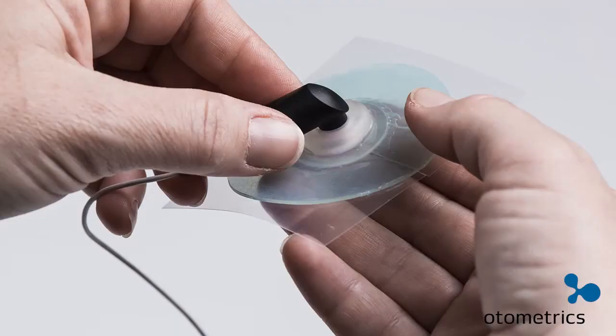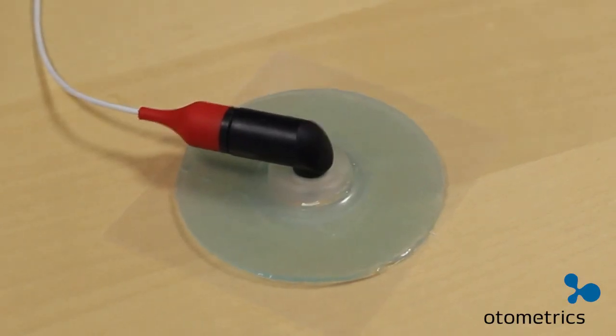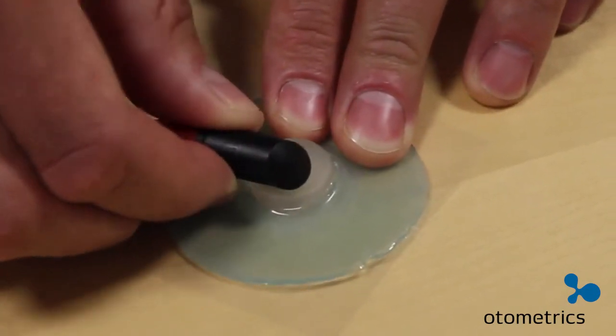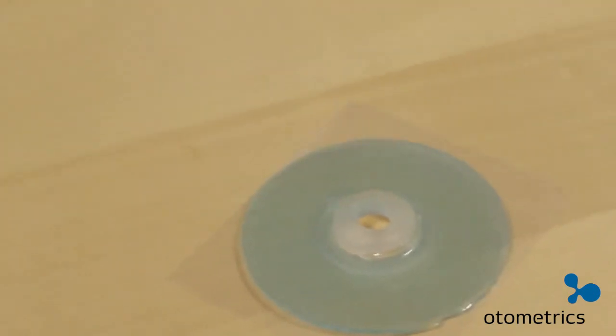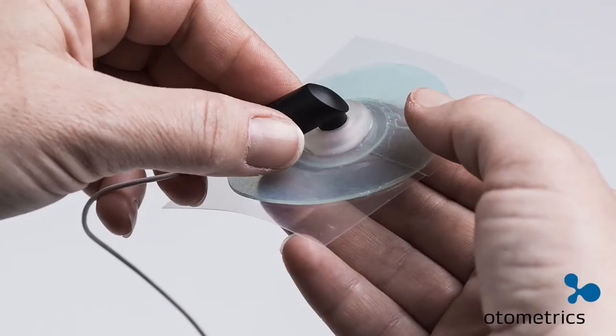When you remove the ear coupler cable transducers from the ear hugs, be careful not to pull the cable. Doing so repeatedly may damage the cable over time. Instead, grab the transducer itself with one hand and the ear hugs with the other and separate the two. While Accuscreen cables are durable and built to withstand normal daily use, they do contain delicate components such as calibrated speakers and data memories that can be damaged if mishandled. Treat them with care and they will last longer.